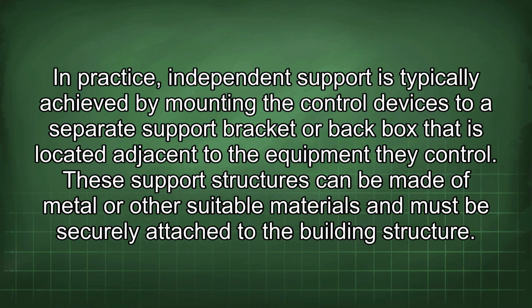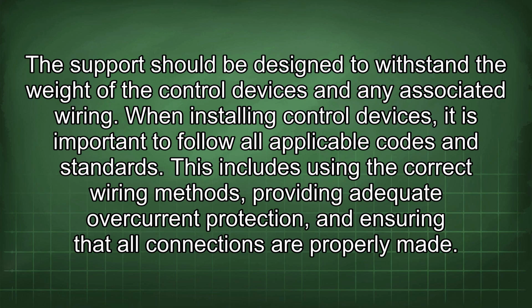In practice, independent support is typically achieved by mounting the control devices to a separate support bracket or backbox that is located adjacent to the equipment they control. These support structures can be made of metal or other suitable materials and must be securely attached to the building structure. The support should be designed to withstand the weight of the control devices and any associated wiring.